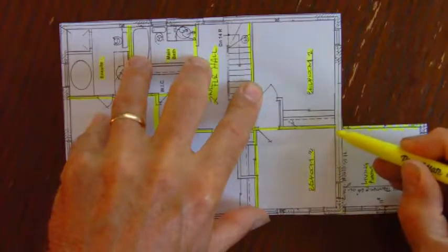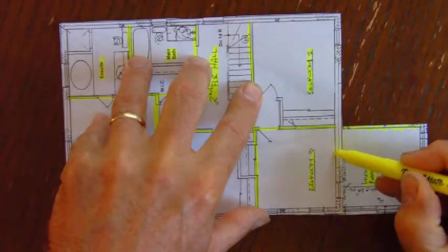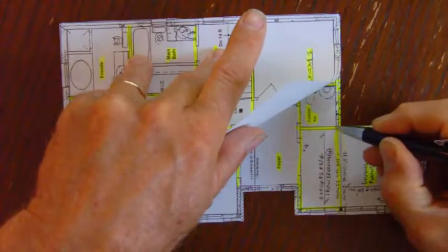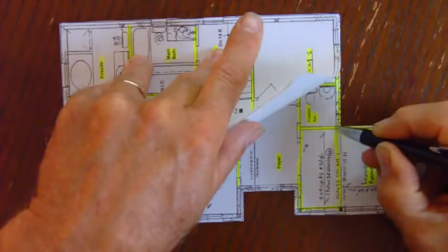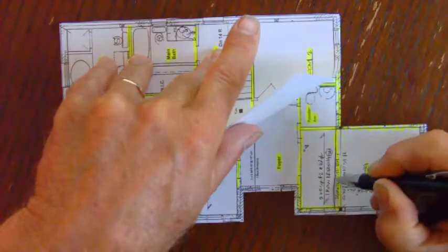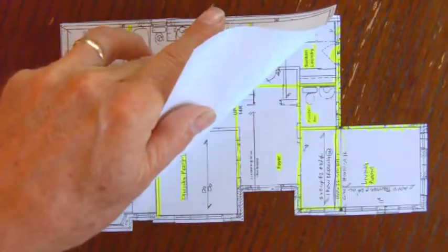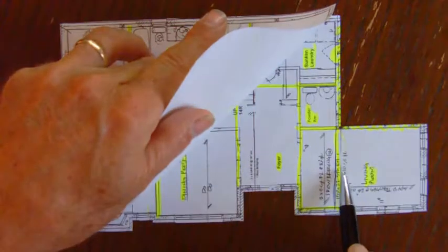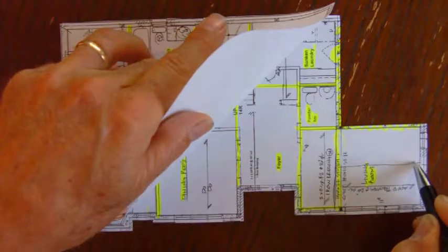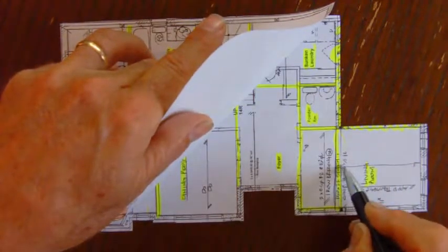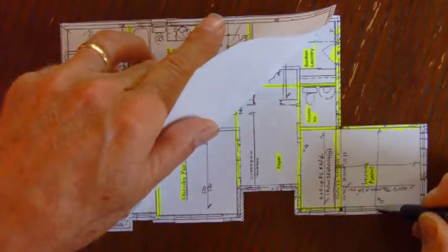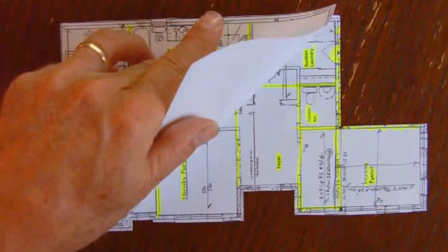And because heat loss starts at the inside surface, you would want to ensure that your heat loss area for your ceiling actually starts also in line with the inside surface of the second floor, so that this entire distance here through here could be the length of the exposed ceiling, and this distance would be the width of the exposed ceiling.